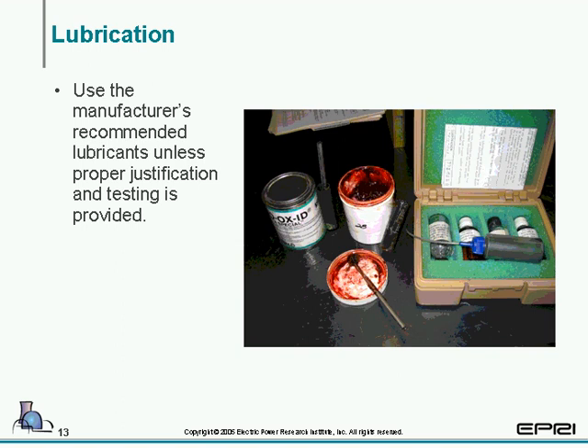We're going to get back to actually looking at the switchgear in a minute. Right now I'd like to talk a little more about lubrication. The manufacturer recommended lubrication is what you should use unless you have justifications for changing it. Some of those reasons are that some manufacturers throughout the years have actually changed the lubrication that they use, and you should follow that. And if you have multiple vendors or manufacturers in your plant, then you need to take care and caution not to mix the lubrication between each other or other types of manufacturers on their equipment.